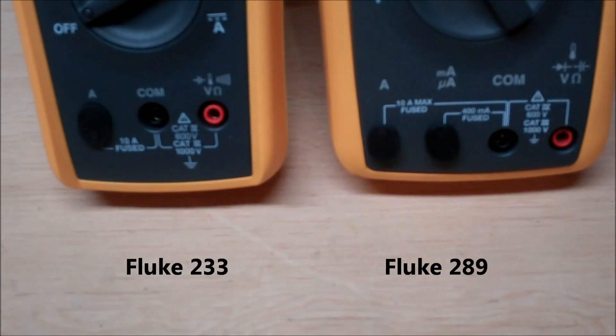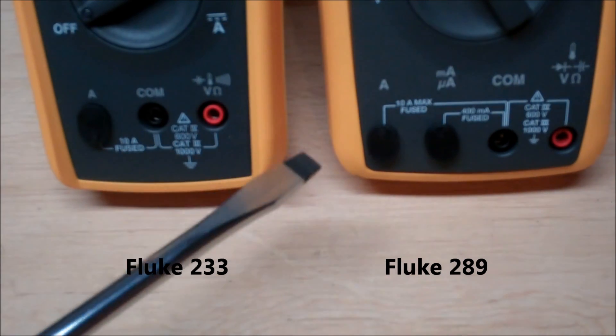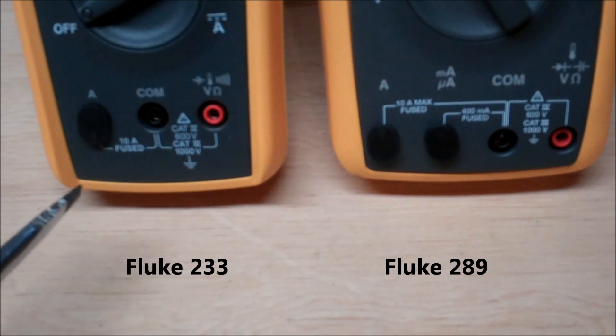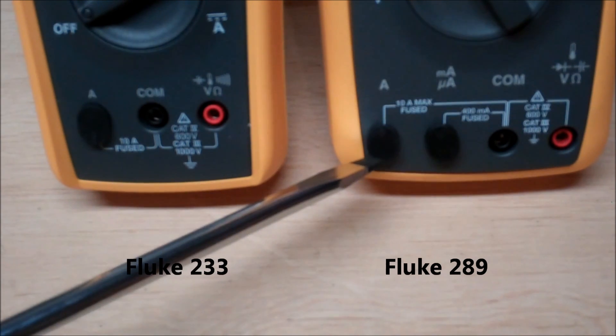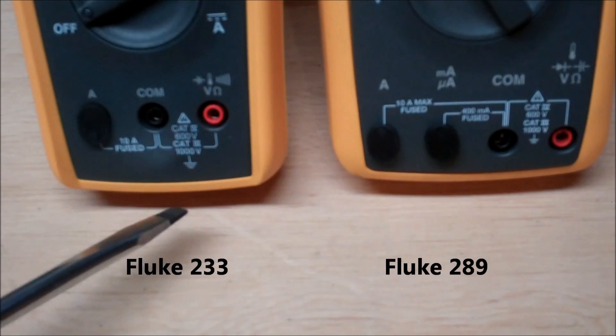Now one negative aspect I've got to focus on here on the Fluke 233 is that it only has three terminals. And what that means is you can't really measure microamps with this. Where if you compare it to something like the Fluke 289 it's got a microamps and a regular amps jack. So this has a lot more versatility where something like the Fluke 233 is pretty well a dedicated electrician's meter.